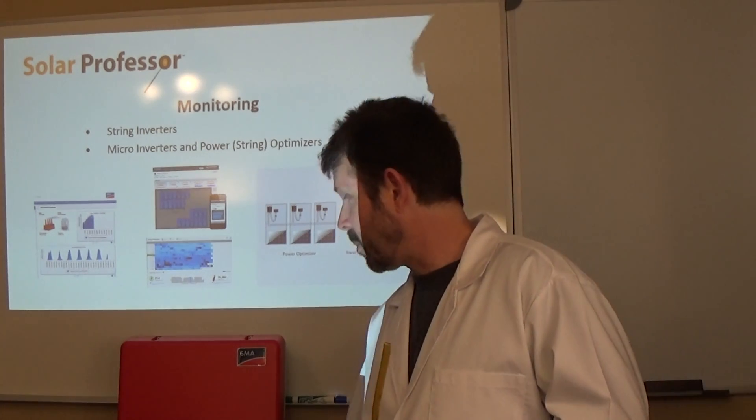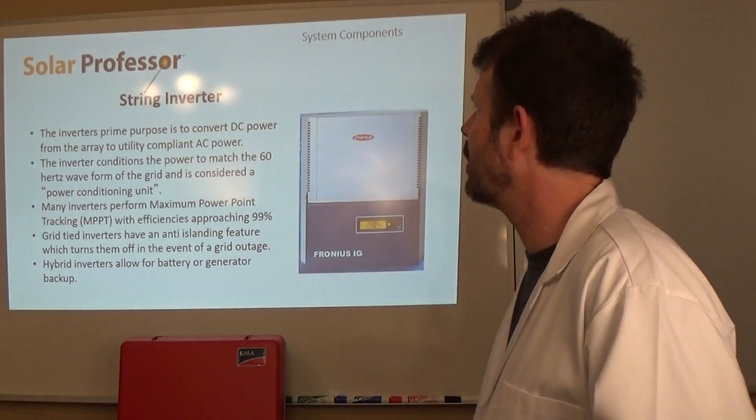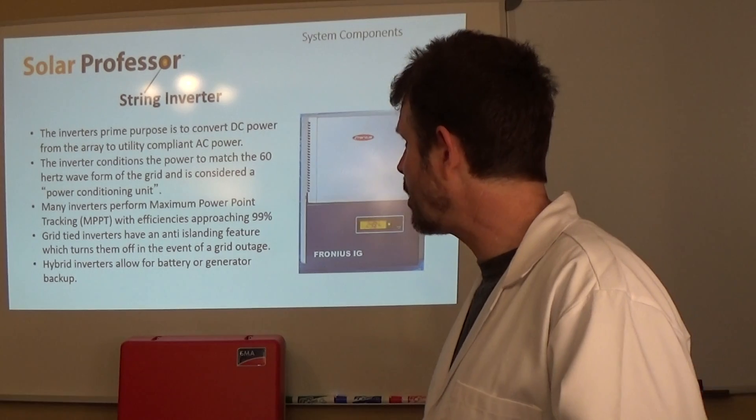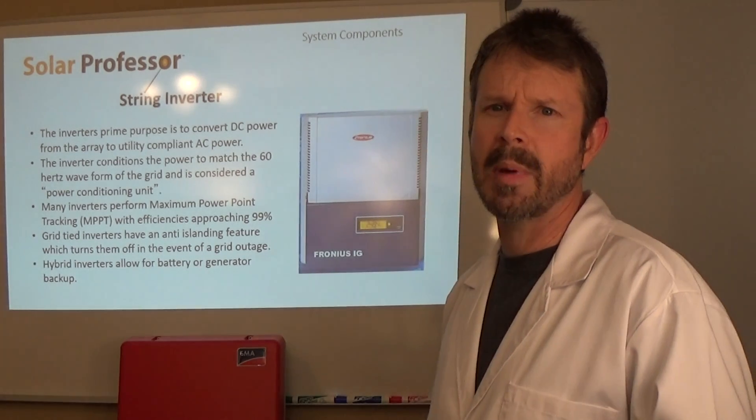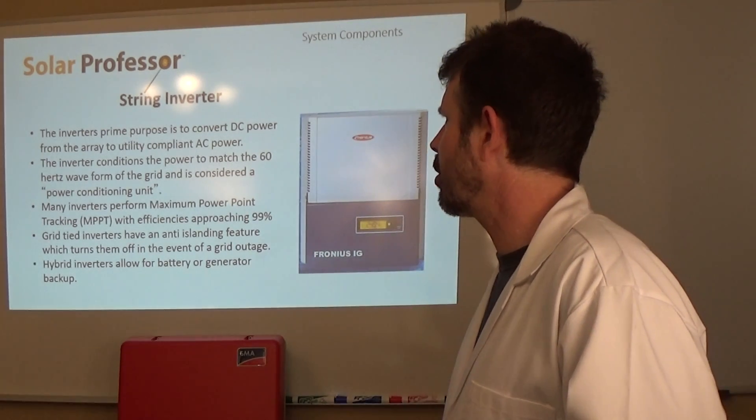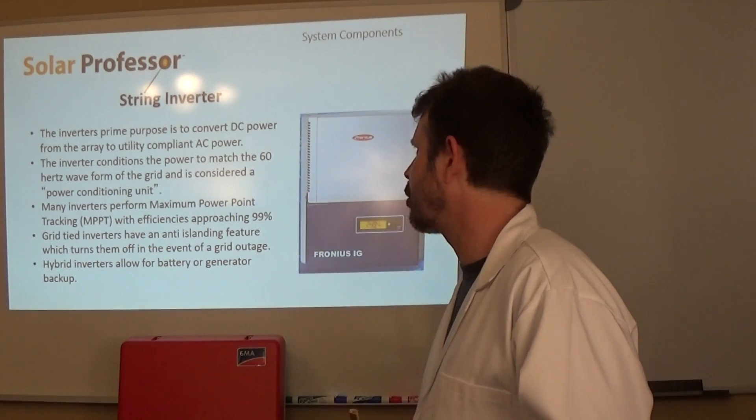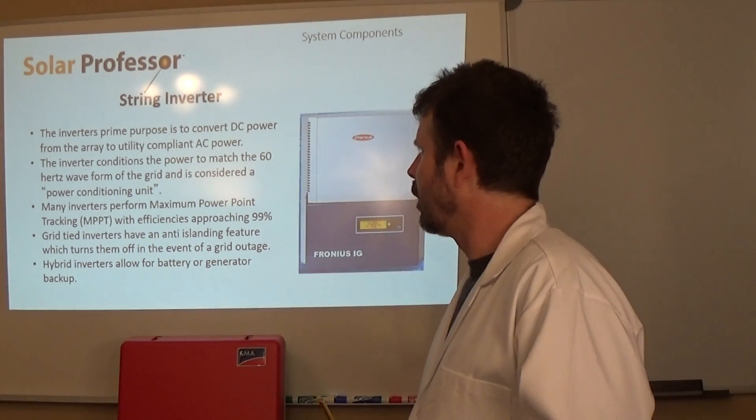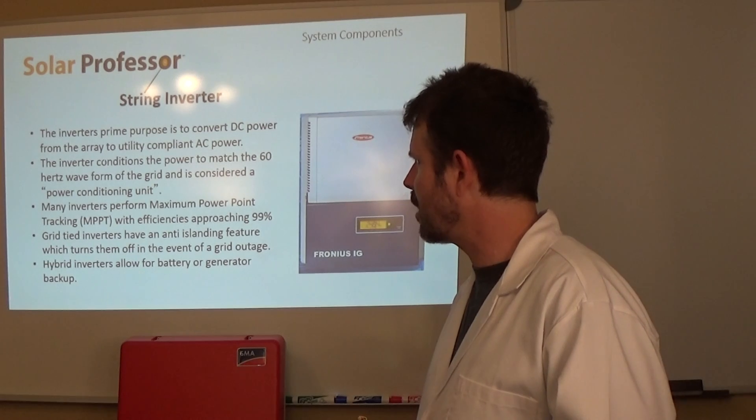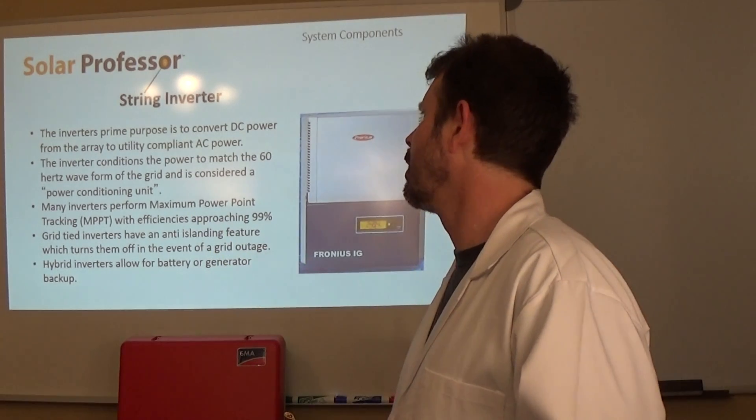Here's the string and specific string inverter. Inverters prime purpose is to convert DC power from the array to utility compliant AC power, so it has to match the power grid. The inverter conditions the power to match 60 Hertz waveform of the grid and is considered a power conditioning unit. Many inverters perform maximum power point tracking at 99% efficiency.